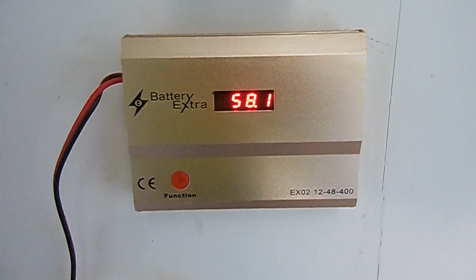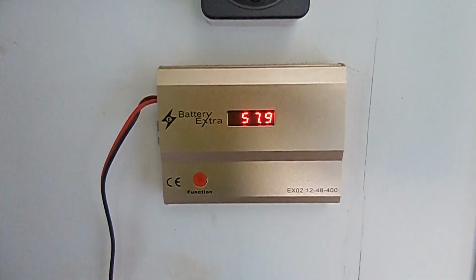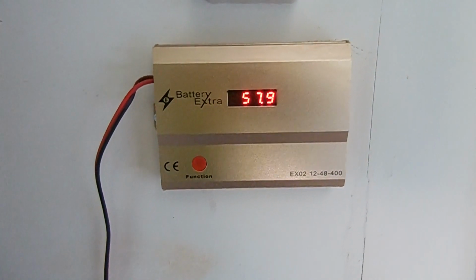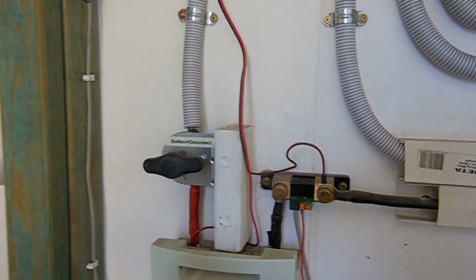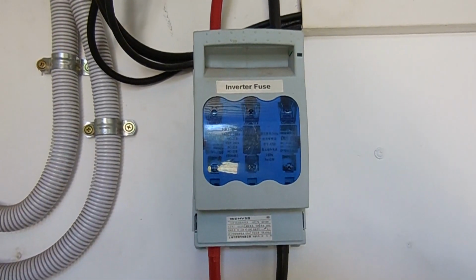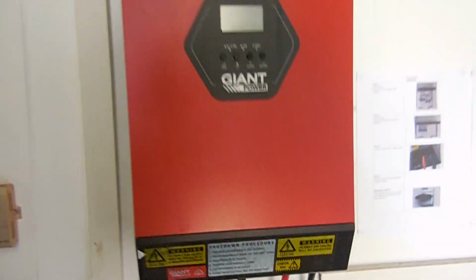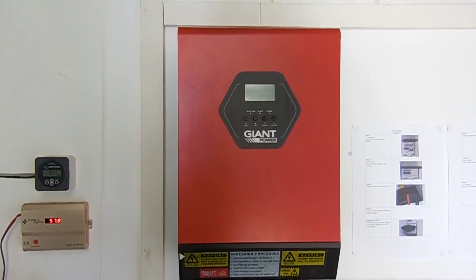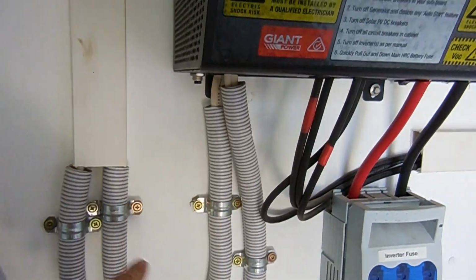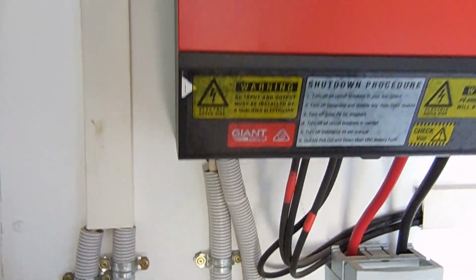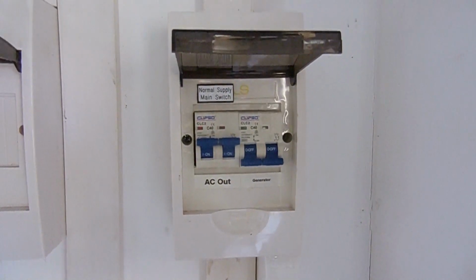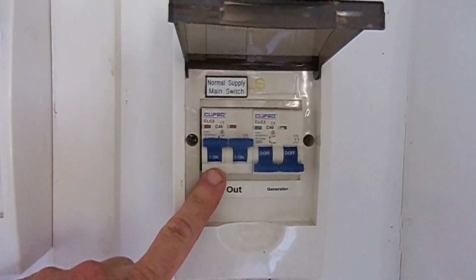This is also a battery pulsar, which is supposed to pulse the batteries to remove sulfate and give them extra life. So after the battery disconnect and the negative side here, it comes across and goes into this other fuse box, which then leads into the DC input of the inverter. On the AC side of the inverter, we've got the AC power coming out, which goes through this conduit along the wall here, and then we've got a couple of AC breakers that go to the power panel on the house. So we've got an AC out.